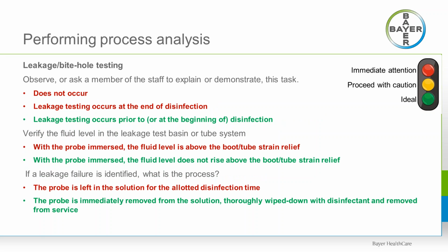So at the end of 2015, the IAC established a requirement that leakage testing on all TEE probes must occur between each patient study, and that the results of the testing must be documented. Even though it's been well over a year, not all facilities are compliant. And really, if you're not accredited by the IAC, it's optional. That being said, it's recommended by probe manufacturers that you do perform the leakage testing. And I would expect the Joint Commission to really introduce this in the next year or so.